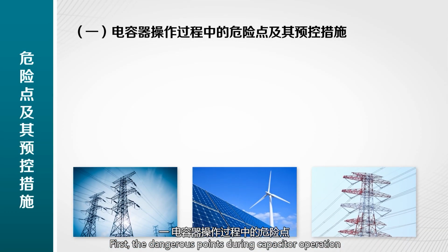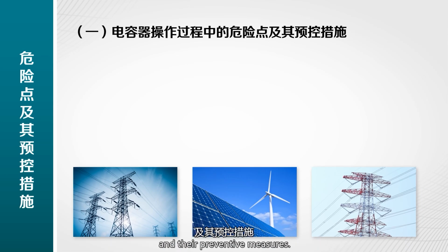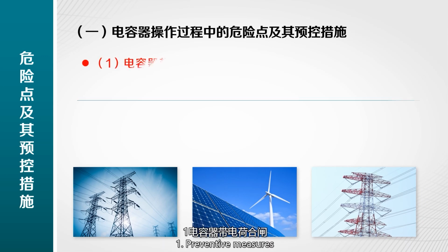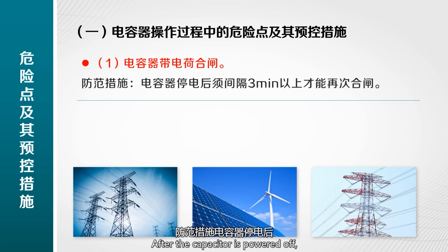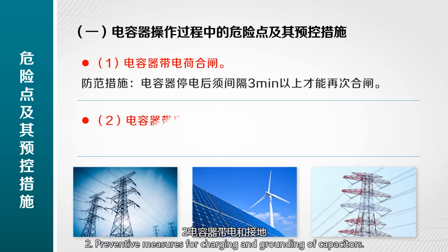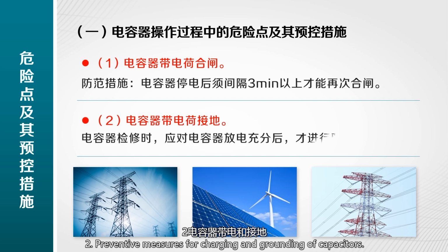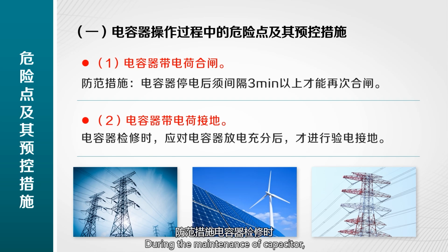First, the dangerous points during capacitor operation and their preventive measures. First, preventive measures for capacitor charge closing. After the capacitor is powered off, it takes more than 3 minutes to close again. Second, preventive measures for charging and grounding of capacitors. During the maintenance of the capacitor, the capacitor should be fully discharged before power inspection and grounding can be carried out.